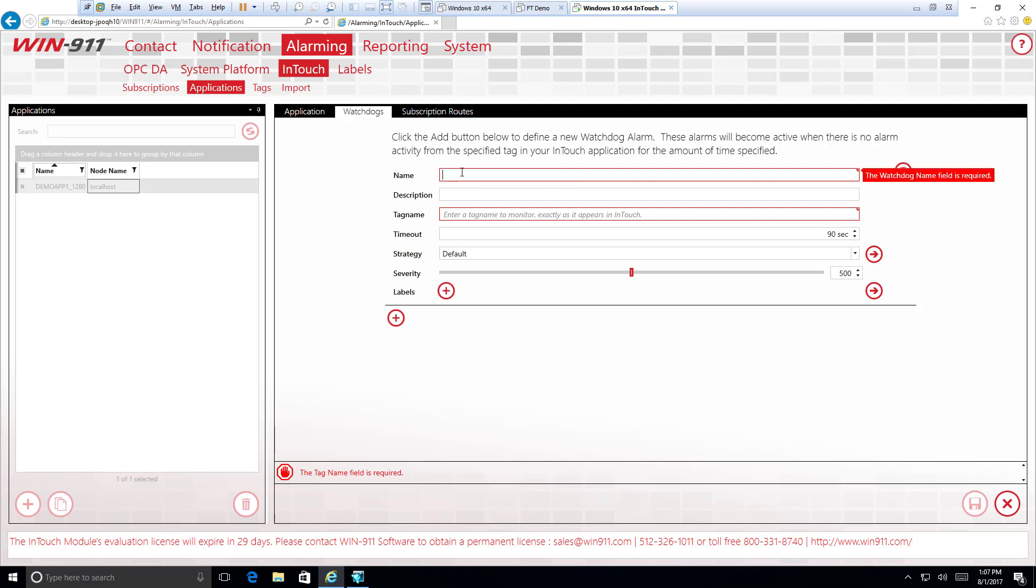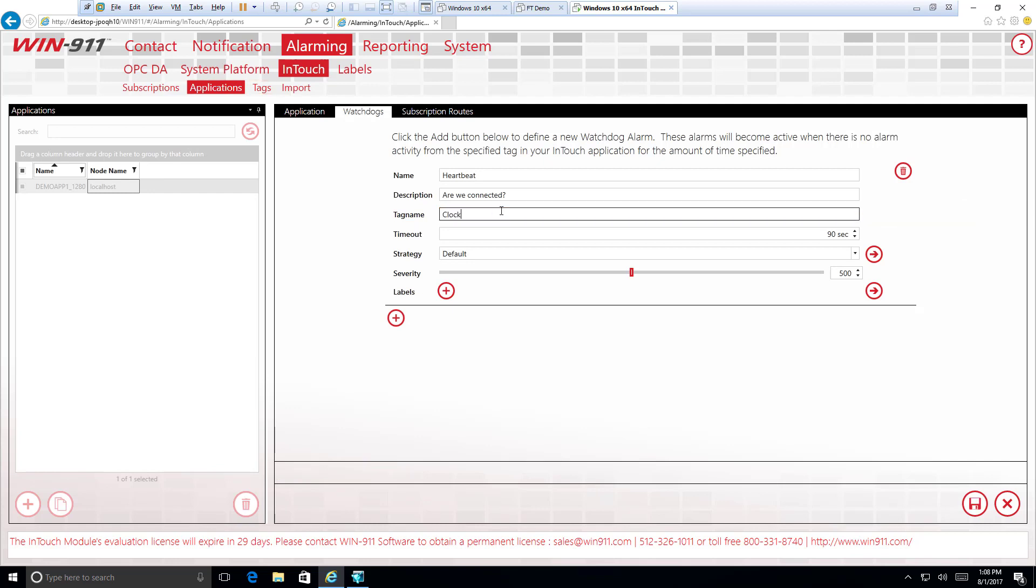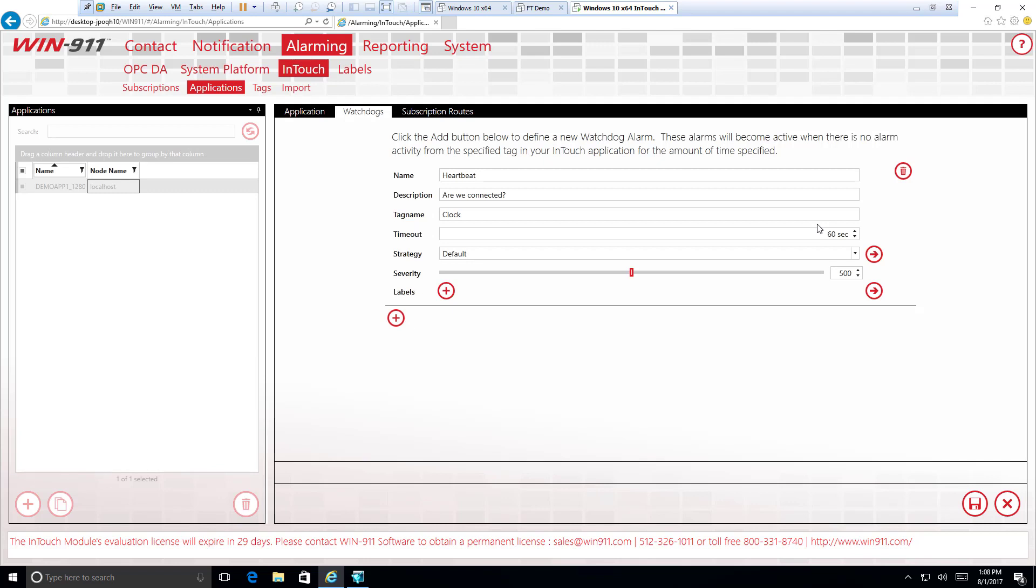If we stop seeing them, then we know there's a connectivity issue, and that's when this watchdog will be activated and send you a notification. So let's name this. We'll call it Heartbeat. It's a nice name. Description. We'll just say, are we connected? Tag name. We could go over to InTouch and take a look at our tags, but we're actually going to be doing that in the next section. Let's just assume we have a tag called clock. And here we go. We go timeout. So generally, there can be hiccups in connections, maybe from InTouch or maybe your connectivity on your network. So a timeout much lower than 90 seconds isn't generally suggested. I could say going 60 seconds wouldn't be too bad. But in general, we default to 90 because it's a pretty safe bet that that is a good timeout period.